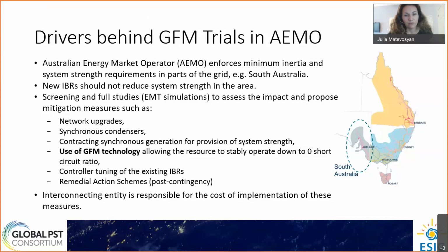And then screening and full interconnection studies with EMT are being done to assess impact and propose mitigation measures such as network upgrades, synchronous condensers, contracting with existing synchronous generators, use of grid forming technology, controller tuning of existing inverter-based resources, and remedial action schemes.